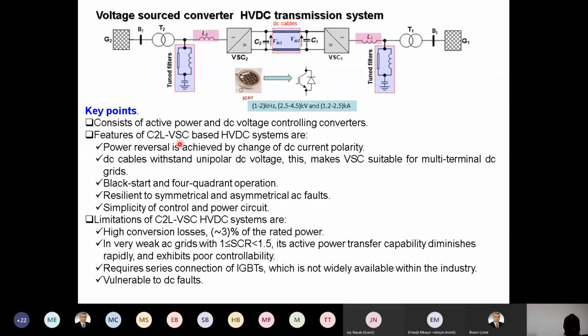And the feature of the conventional two-level converter in HVDC applications is we can reverse the power by changing the current direction. And this is very important, especially in multi-terminal DC applications, because it's easy to keep all the DC voltages fixed. You just change the current direction, so each power flow in the other converters remains independent. And also, the DC cable withstands unipolar DC voltage. This also makes the DC cable for VSC cheaper. And also, it has black start and 4-quadrant operation.